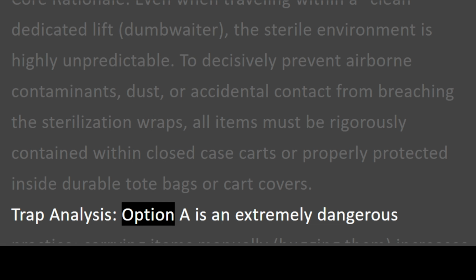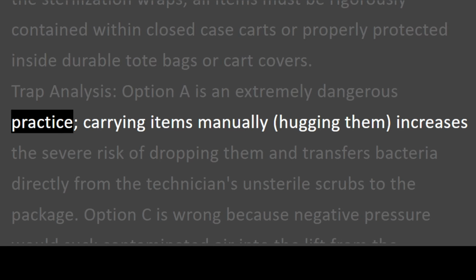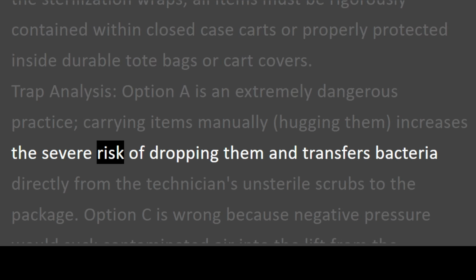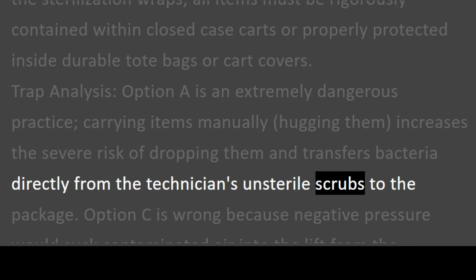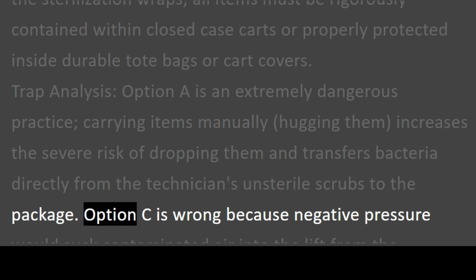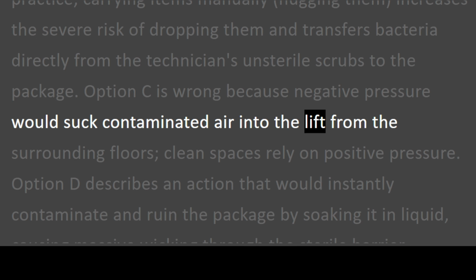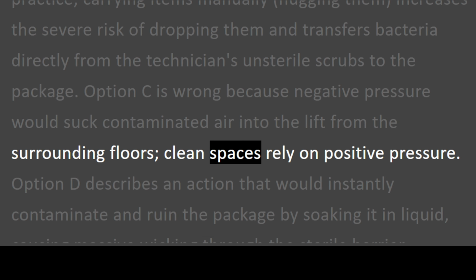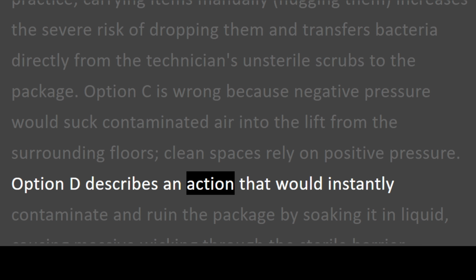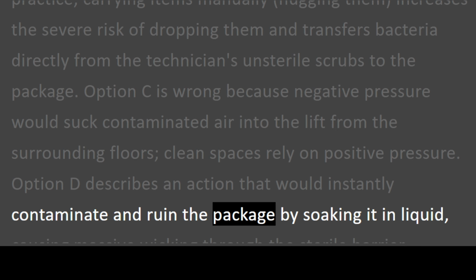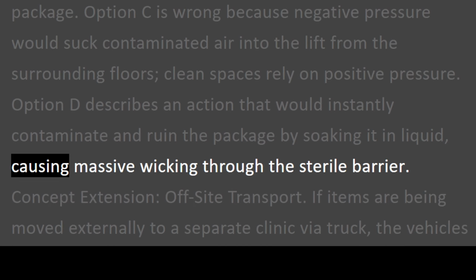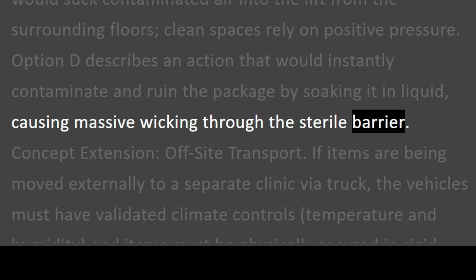Trap analysis. Option A is an extremely dangerous practice. Carrying items manually, hugging them, increases the severe risk of dropping them and transfers bacteria directly from the technician's unsterile scrubs to the package. Option C is wrong because negative pressure would suck contaminated air into the lift from the surrounding floors. Clean spaces rely on positive pressure. Option D describes an action that would instantly contaminate and ruin the package by soaking it in liquid, causing massive wicking through the sterile barrier.